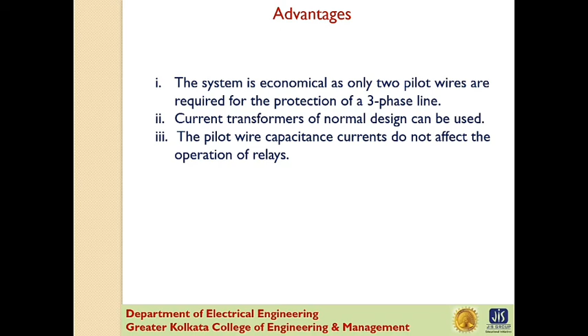Next is the distance protection. Both the time graded and pilot systems are not suitable for protection of very long high voltage transmission lines. The former gives an unduly long time delay in fault clearance at the generating station end when there are more than 4 or 5 sections, and the pilot wire system becomes too expensive owing to the greater length of pilot wires required. This has led to the development of distance protection, in which the action of the relay depends upon the distance or impedance between the point where the relay is installed and the point of fault.